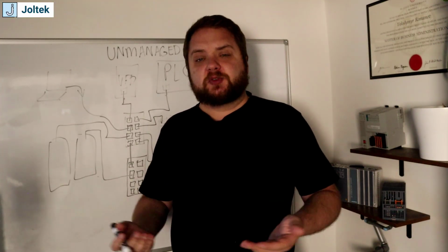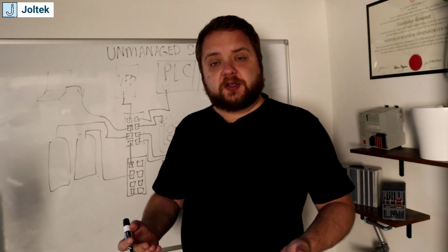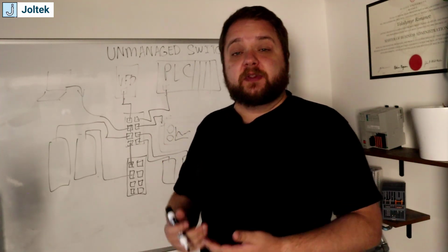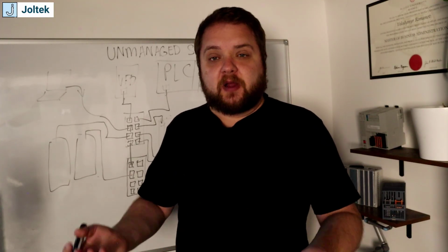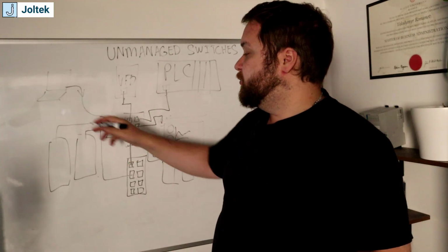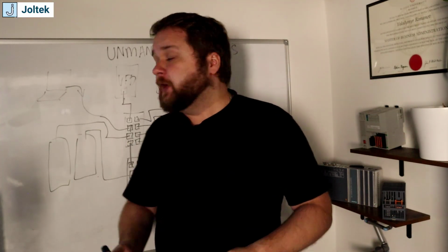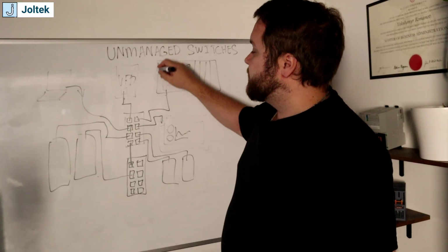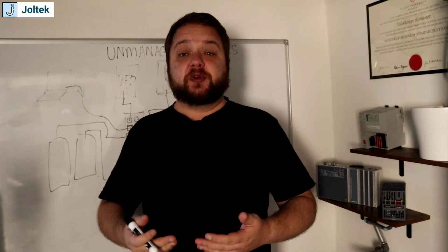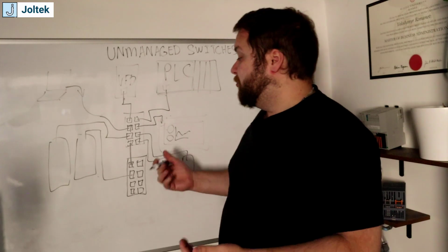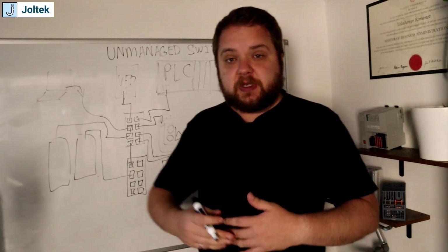Now, of course, this question can come up: what is the limit in terms of traffic? Well, the hard part with unmanaged switches is that you don't have the data. You don't have the ability to see how much traffic is going through the switch by logging into some kind of portal. Of course, we can use Wireshark, so if you communicate from the laptop to the switch, you can monitor the traffic on that specific network. You can also have other options. For example, if you have a PLC and you have access to it, a lot of times it will give you the opportunity to see how much traffic is being consumed by that specific card. But in any case, the point here is that unmanaged switches are going to be completely open.